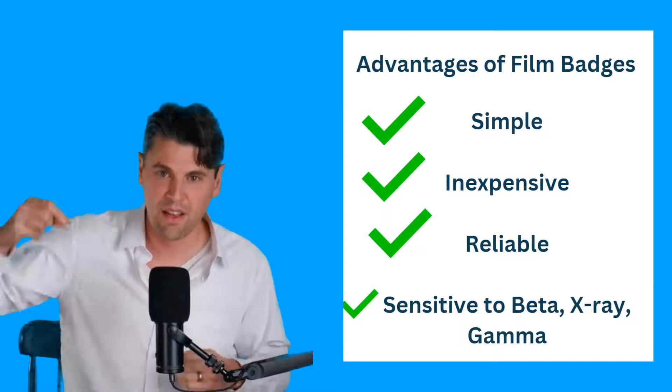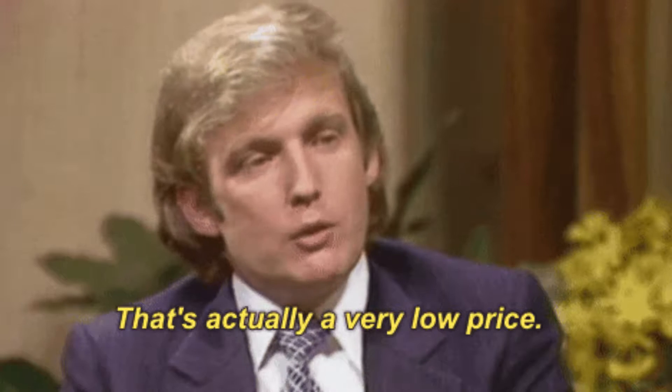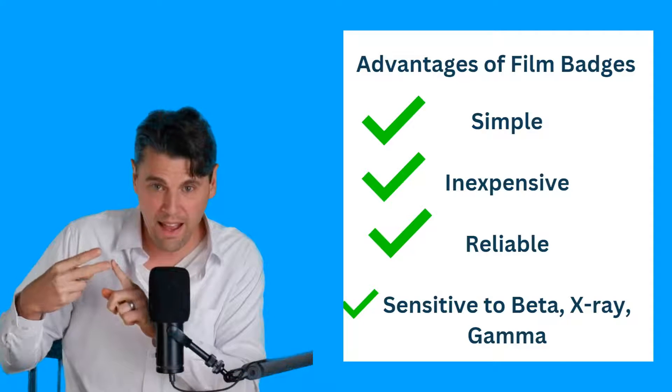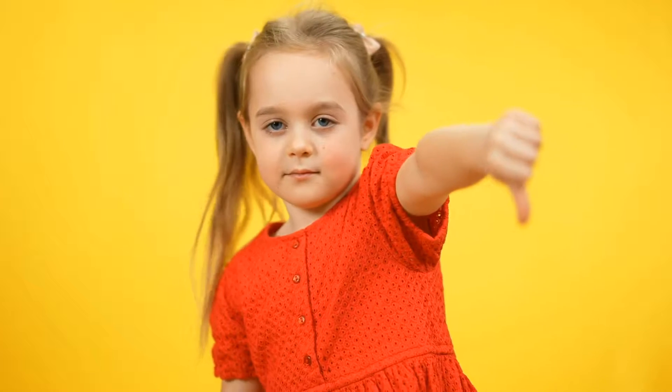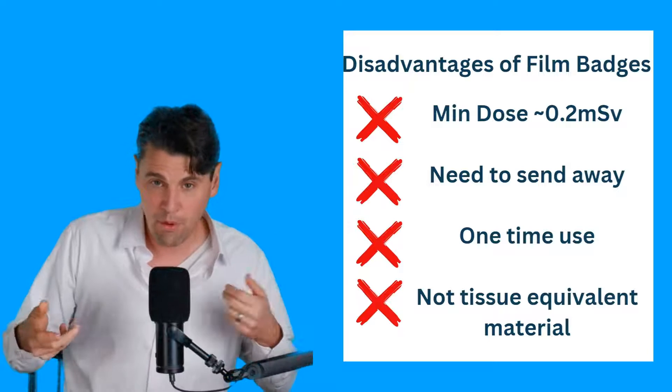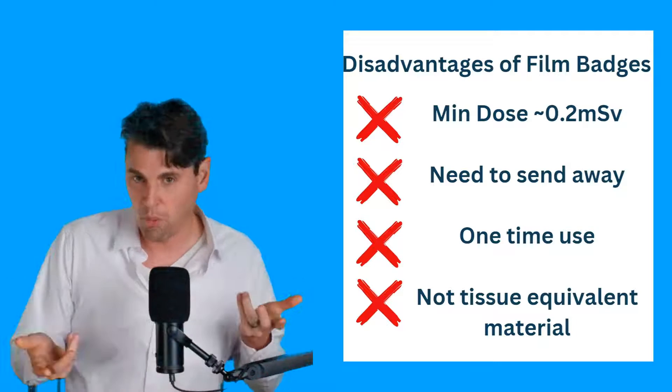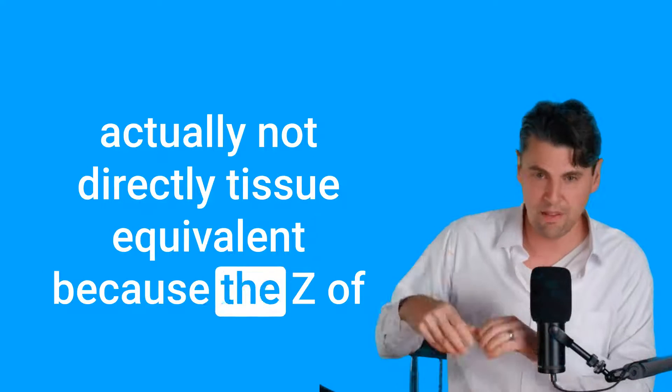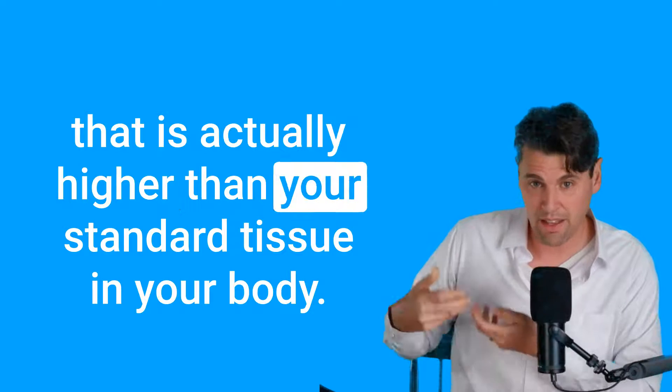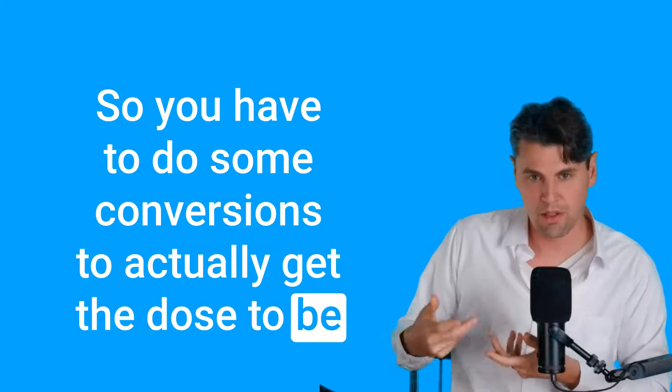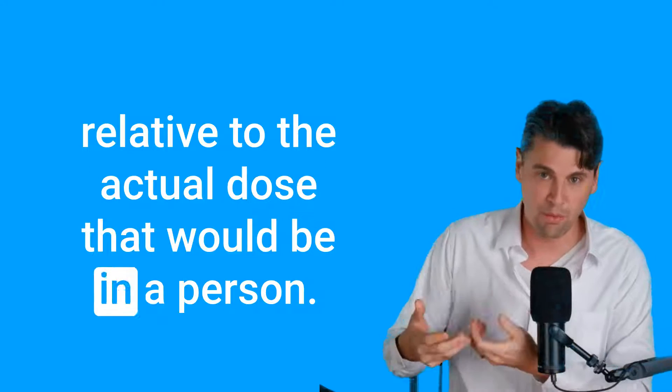Advantages of the film badges, they're simple, they're inexpensive, they're reliable, and you can make them sensitive to all those different beta x-ray and gamma, like we talked about. And disadvantages is that they're not good at measuring extremely low doses, you need to send them away to do the film processing and to do the measurements. They're a one time use. And because it's actually silver in the film that you're looking at the interactions with, it's actually not directly tissue equivalent, because the Z of that is actually higher than your standard tissue in your body. So you have to do some conversions to actually get the dose to be relative to the actual dose that would be in a person.